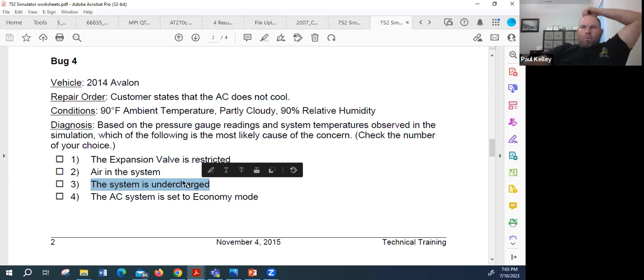How do you think we could test to see if the TXV is restricted? Temperature before the evaporator, and temperature: 110 coming in, 5 coming out. How the heck did it get to 5? That's a huge difference. Let's go with a default, just for fun.